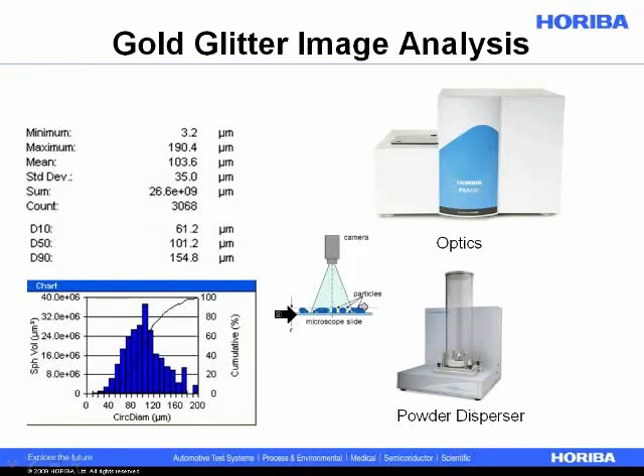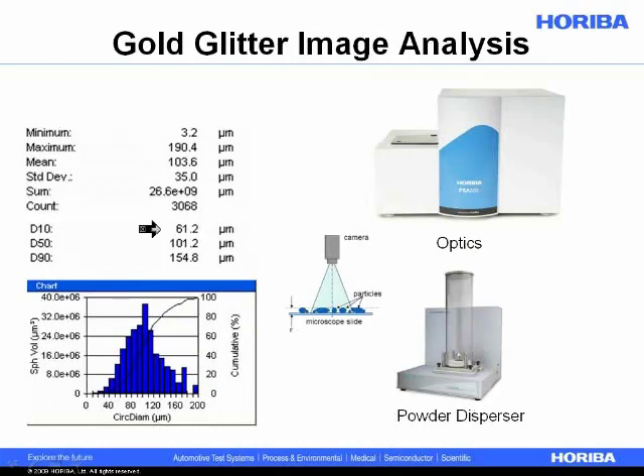The slide is brought into the instrument, and as the slide moves, we take images of the particles. For every image we take, we assign size and shape values to those particles. We used the PSA 300 to do a measurement of the same glitter powder. The results are fairly similar: a D90 near 150, a D50 at 100, and a D10 at 60 microns.